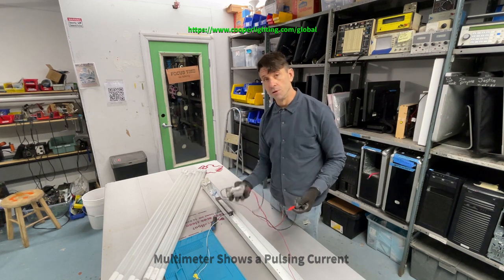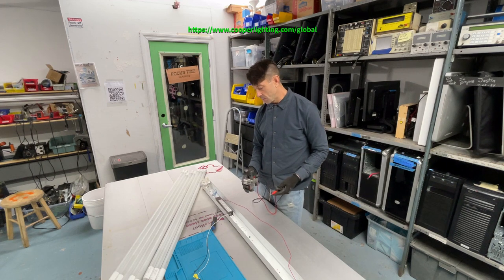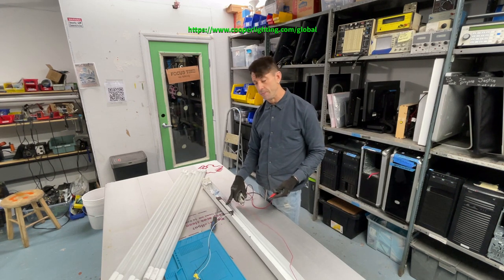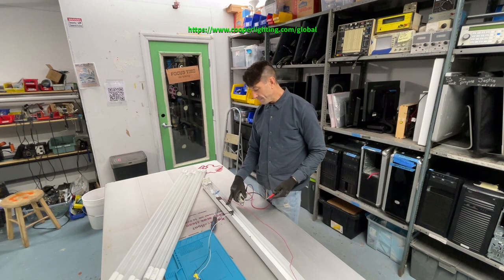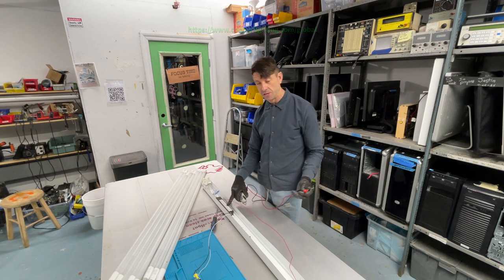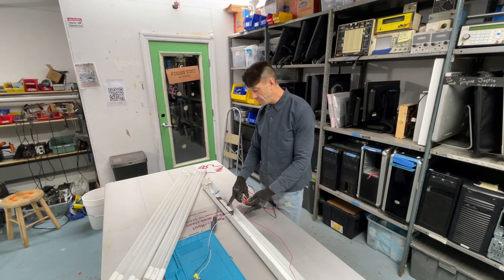When you're testing the ballast to see if it works, it doesn't actually give a steady output reading. This ballast was made by Cooper Lighting. The only thing it shows is an input range of 120 all the way up to 277 volts, at 50 to 60 Hz.